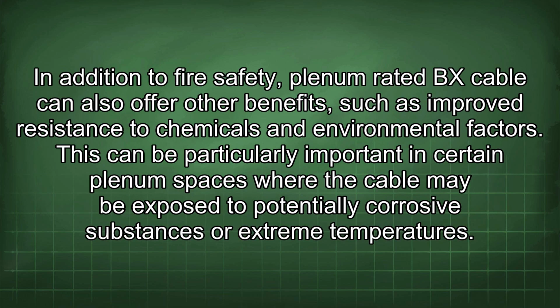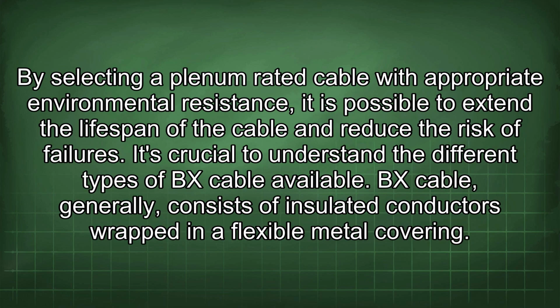In addition to fire safety, plenum-rated BX cable can also offer other benefits, such as improved resistance to chemicals and environmental factors. This can be particularly important in certain plenum spaces where the cable may be exposed to potentially corrosive substances or extreme temperatures. By selecting a plenum-rated cable with appropriate environmental resistance, it is possible to extend the lifespan of the cable and reduce the risk of failures.